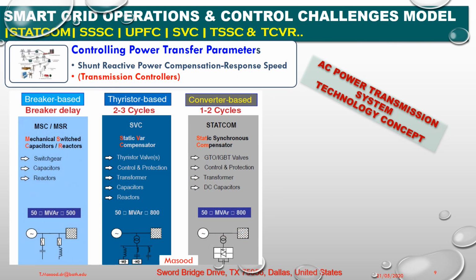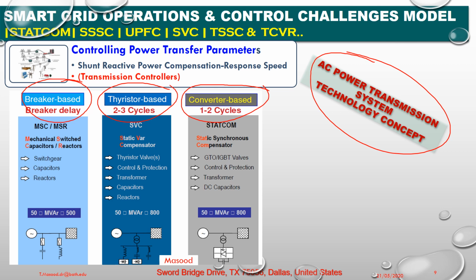Okay, this is a very important slide to address the time-based contingencies. Okay, first generation is circuit breaker based, second is thyristor, and third is converter based. Okay, breaker based is used by the mechanical switched capacitor reactors, and in thyristor based we use thyristors, control protection, transformer, capacitor and reactors, and the STATCOM: GTO, IGBT, control protections and transformer. That is the different configuration each device has. Okay.